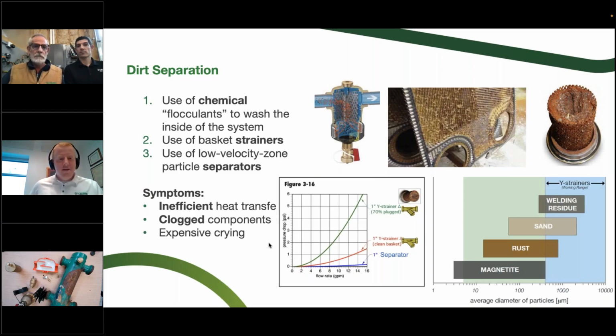The problem with a strainer in these systems is that you can't just pull it out real easy and look at it like an air filter in a forced air system. You've got to be able to get that system wet. Now, when you look at that strainer in the upper right corner, that's not just an easy blowdown. You're yanking that thing out of there, you're banging it on the ground, you're washing it all out, and more than likely you're not going to have isolation on either side of it, so you're isolating large portions of the system or even draining down the system in some cases.